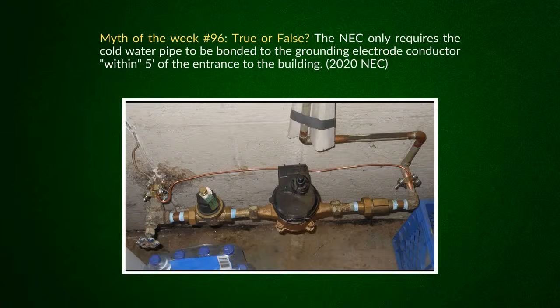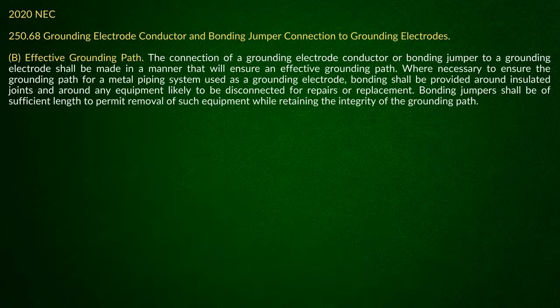You know, in your case, James, you have maybe a water softener, but anytime you have a water softener, meter, or backflow preventer, those are non-conductive pieces, and you have to jumper them so that you maintain the continuity of that metal water piping throughout the structure. Correct. When you go look at your grounding electrodes, you're going to look at 250.52(A)(1) in this case for the metal water pipe. And basically it's going to tell you that you can use it as a grounding electrode, and that has to be connected. In your installations, you go over to 250.68(C)(1), and that's where it's going to tell you you're connecting within 5 feet and all that stuff. Okay. Right. Now, when you get over here, we're still in 68.